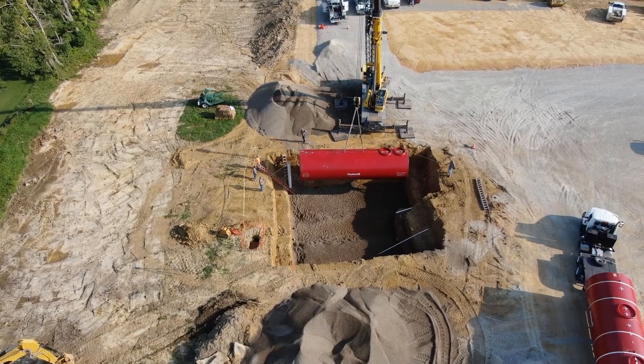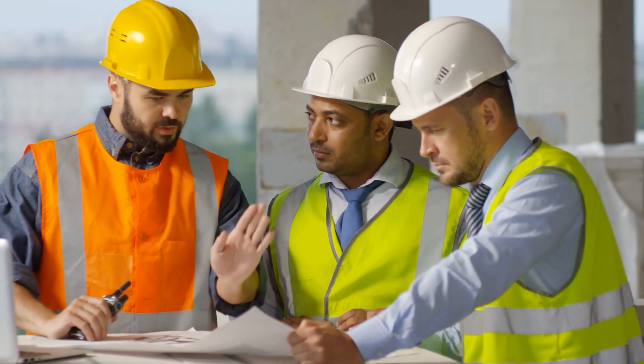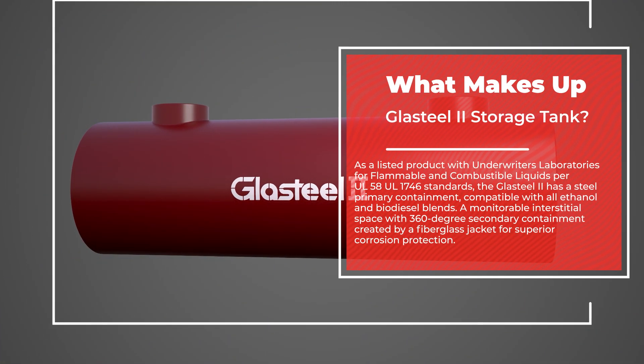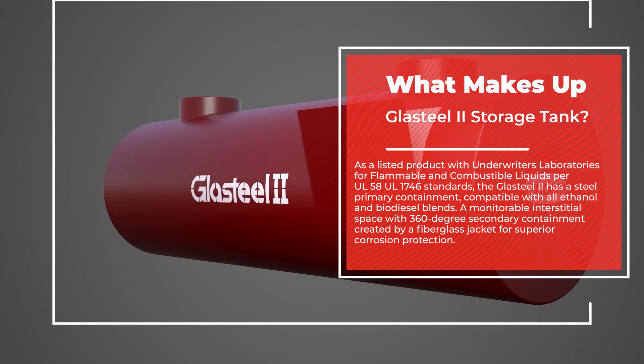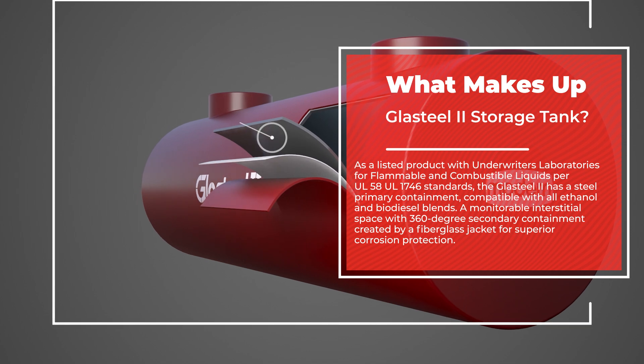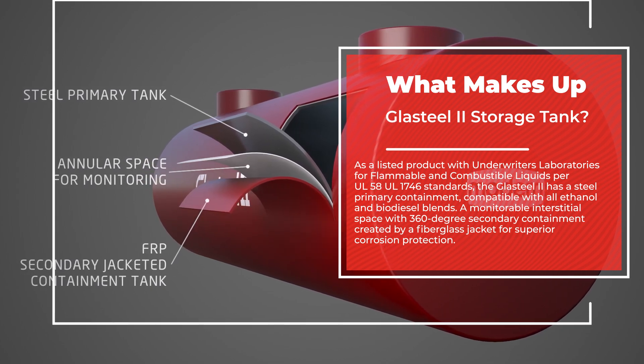The installation of underground storage tanks is a specialized craft. Modern assumes that persons using our installation instructions have a fundamental understanding of the essential procedures of pipe fitting, earthwork and related construction techniques. What makes up a Glasteel II storage tank? As a listed product with Underwriters Laboratories for flammable and combustible liquids per UL58 and UL1746 standards, the Glasteel II has a steel primary containment, compatible with all ethanol and biodiesel blends, and a monitorable interstitial space with 360-degree secondary containment created by a fiberglass jacket.